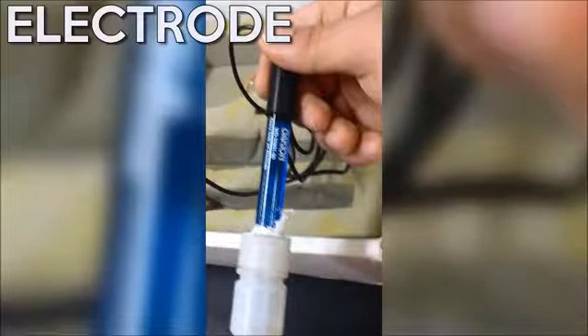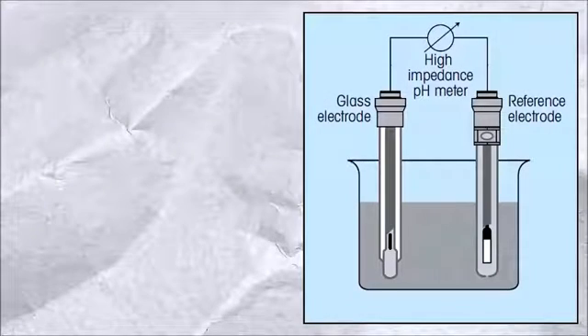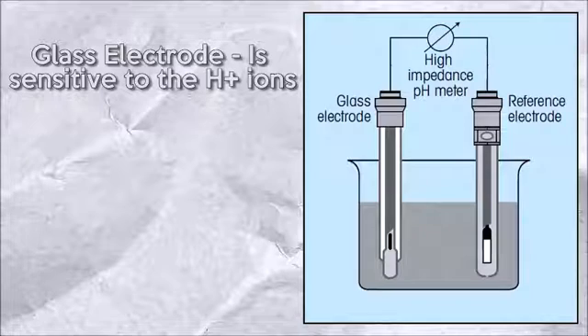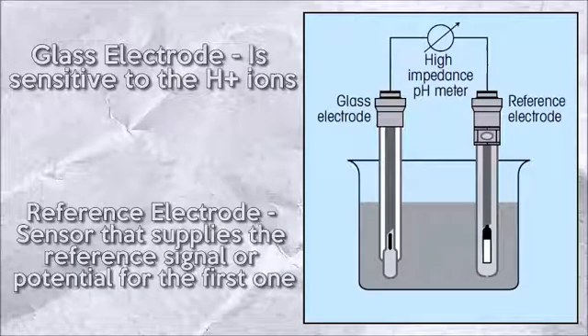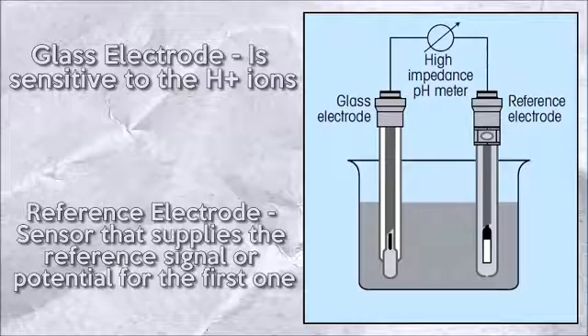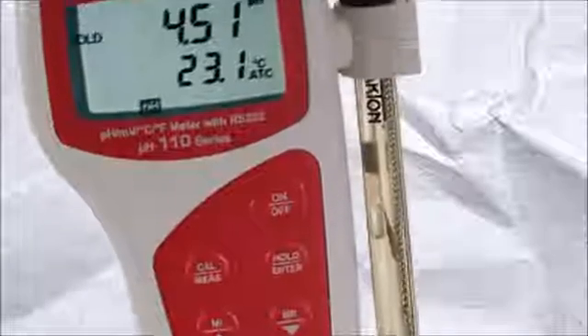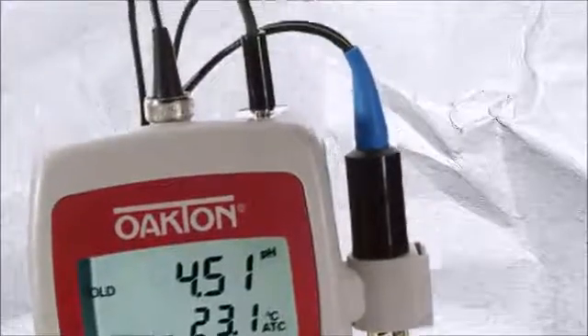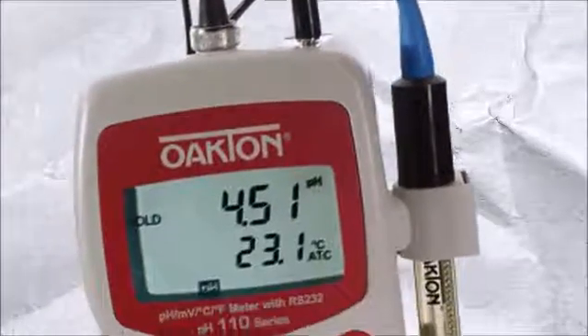This measurement is done by the electrode, which nowadays is combined by two other electrodes. The glass electrode, which is sensitive to the hydrogen ions, and the reference electrode, which functions as a sensor that supplies the reference signal or potential for the first one. This little guy sends the data to the pH meter by a cable and displays it on the LCD screen.